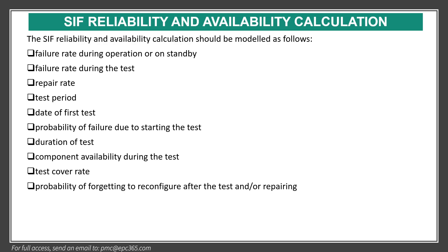SIF reliability and availability calculation should be modeled as follows: failure rate during operation or on standby, failure rate during the test, repair rate, test period, date of first test, probability of failure due to starting the test, duration of the test, component availability during the test, test coverage, and probability of forgetting to reconfigure after the test or repairing.